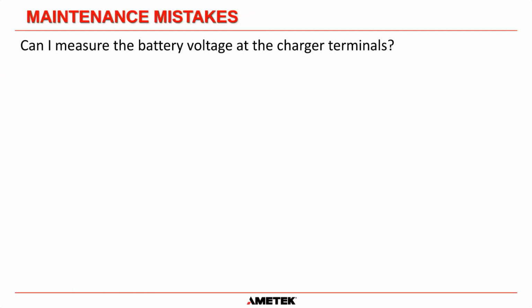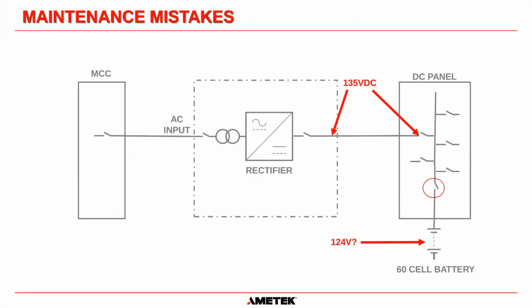Another maintenance mistake is, can I measure the battery voltage at the charger terminals? And the answer to that is no, you should not be doing that. In this circumstance, if we measured at the charger terminals, we would get 135 volts DC. These breakers are drawn open, but they are actually closed. And then this one here is closed. We would measure 135 volts DC. But this one here, the battery breaker, for some reason has been left open.